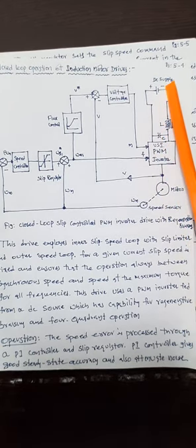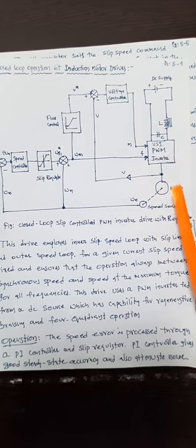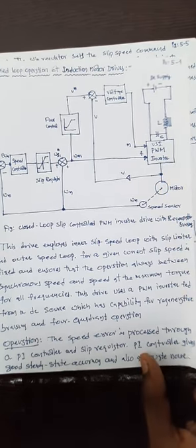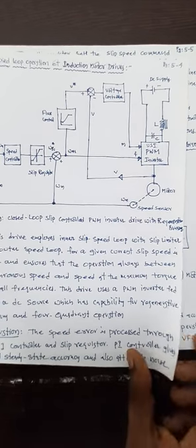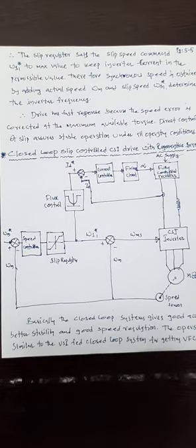You see here, a DC supply is directly given to the PWM inverter, so no extra arrangement is required to change the voltage. But here, a CSI inverter operates in the stepped wave inverter mode, so the drive does not have the ability to change the voltage. That's why you give the AC supply and keep a fully controlled rectifier, so that AC supply is converted into DC supply by firing angle control, so a variable voltage is obtained, and the variable voltage will change the current.